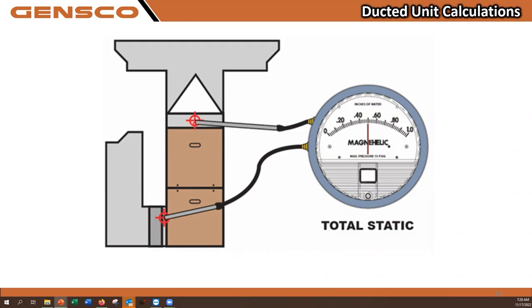If you're doing this on a unit with a cooling coil, you have to be between the furnace and the coil. If this is say a gas furnace, but if this is a Mitsubishi SVZ, you want to be on the outlet side of the air handler. And if you've got an electric heat strip, by the way, you have to take this measurement between the outlet and the heat strip, because the heat strip is going to have a pressure drop, in order to get an accurate total external static pressure.